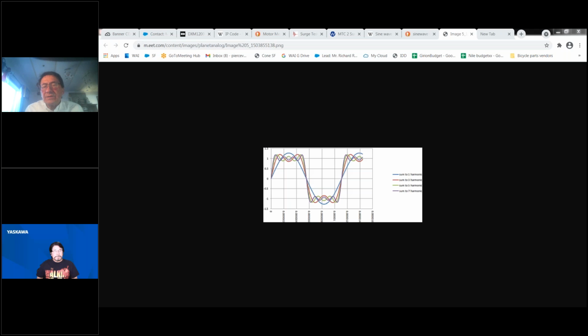So that's what led to this investigation, if you will, because we really need to solve this problem for the industry. More and more of these submersibles are going on VFDs for very good reasons. You need to vary the speed on your pumps, and therefore you need a variable frequency drive. So the immediate solution when we suspected DVDT or voltage spiking was to use a DVDT filter on the output of the standard VFD. And that's called a low pass filter.